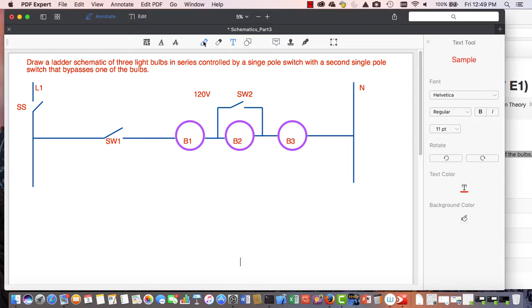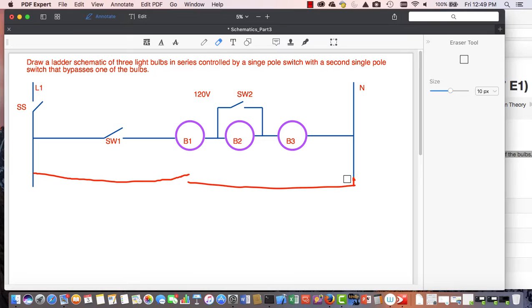Now, a lot of people are tempted to do this, but don't do it — this would be incorrect. If I connect that into there, that's incorrect, because this switch would then close and create a direct short circuit that would blow out a transformer or a circuit breaker.